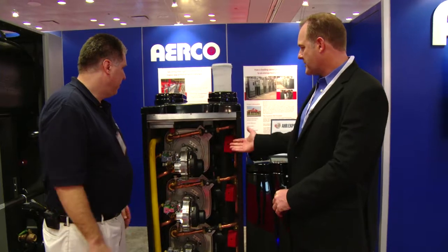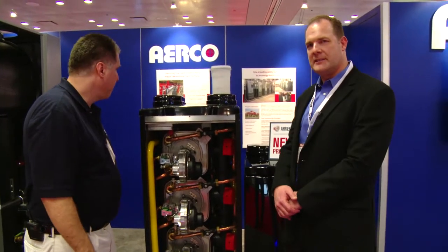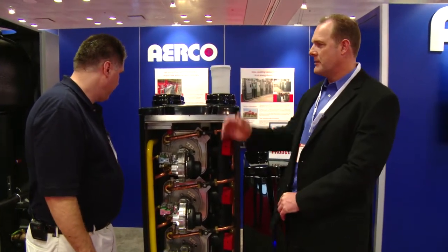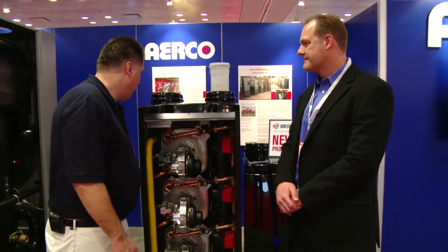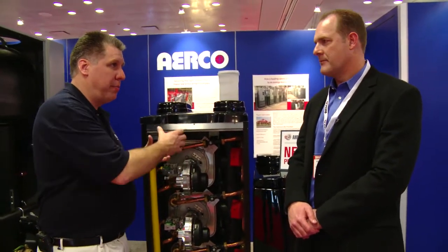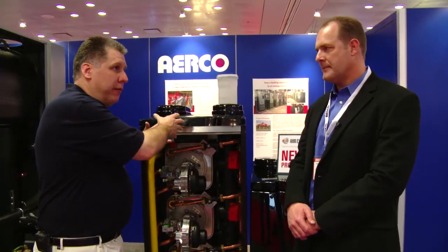There you go. These also have the ability to be vented with PVC venting, either directly out the sidewall or up through a roof. On the back, we're not going to walk around there, but I saw what's called a low-loss header or a hydraulic separator. That comes from the factory built in, or is it field pipe? Right, that comes from the factory built in. Most water tube designs, unlike our fire tube Benchmark boilers, have less ability to vary flow as much. So we apply this with a low loss header. That really reduces a lot of complications, especially in a variable flow system.